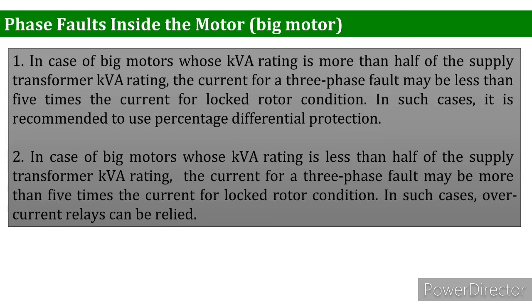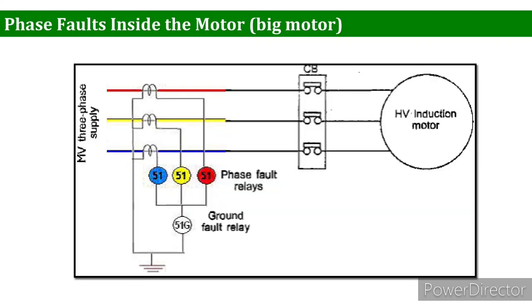The second case is big motors whose KVA rating is less than half of the supply transformer KVA rating. The current for a three-phase fault may be more than five times the current for the locked rotor condition. In such cases, overcurrent relays can be relied upon. So you have the two cases of big motors, and there is a difference in which relays have to be used and when. So what is the strategy for protecting big motors?